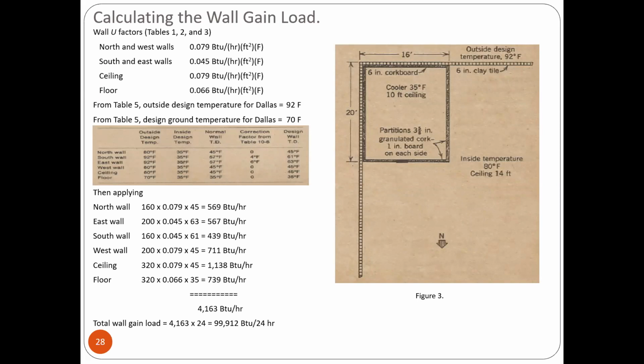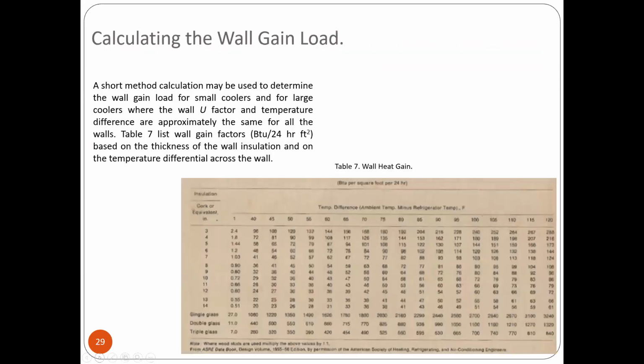Okay. So the area is the outside dimension. Okay? So, ito sa cold storage. Pero sa aircon, that is inside dimension ang ginagamit ko. Now, calculating. A short method may be used to determine the wall gain load for small coolers only and for large coolers where the U factor and temperature difference are approximately the same for all the walls. Assuming lang. So, para hindi ka na magpare-parehas, may shortcut. Kaya lang, iwas lang yung shortcut, baka may iba palang materials, okay?